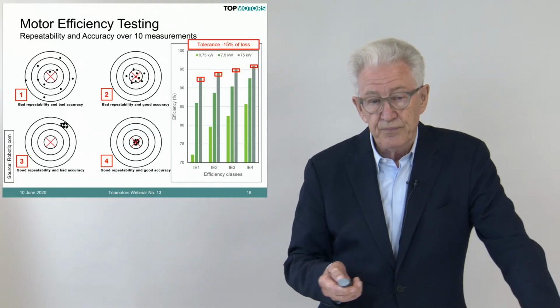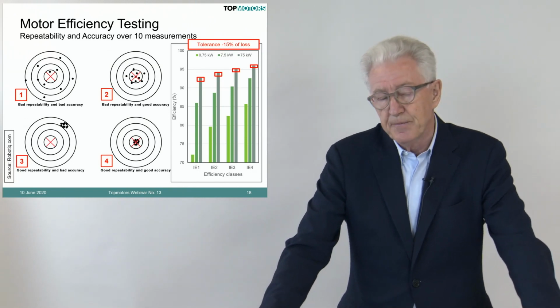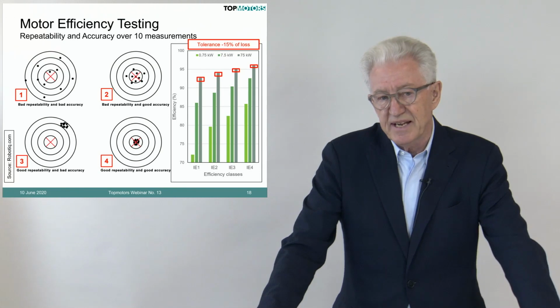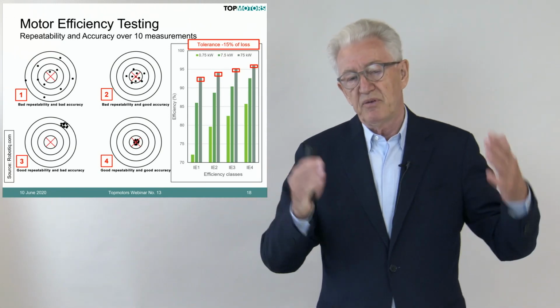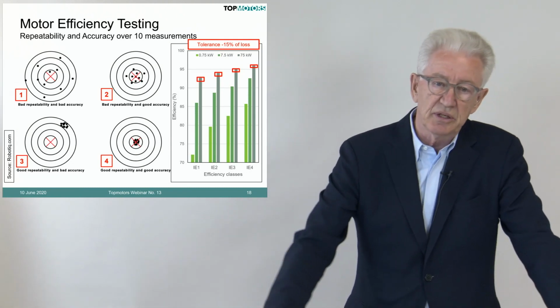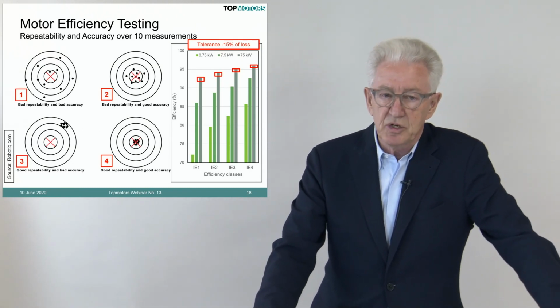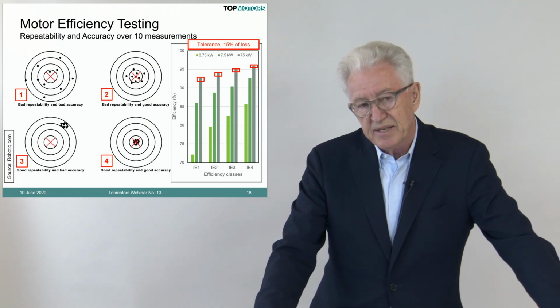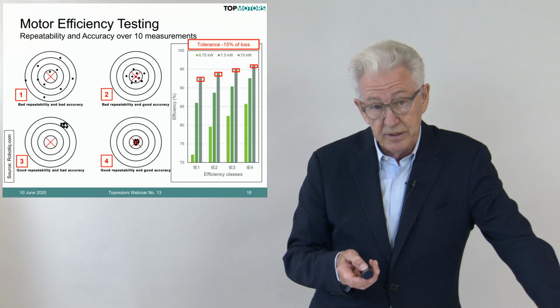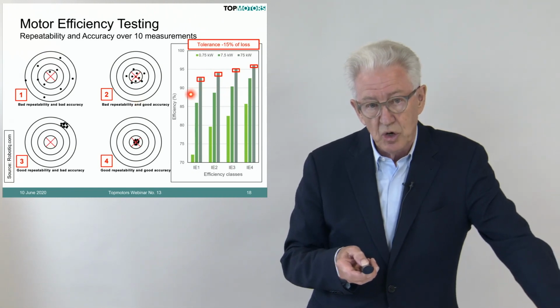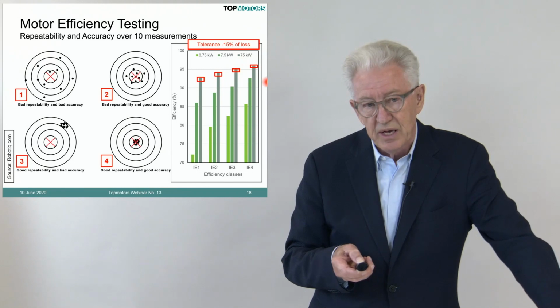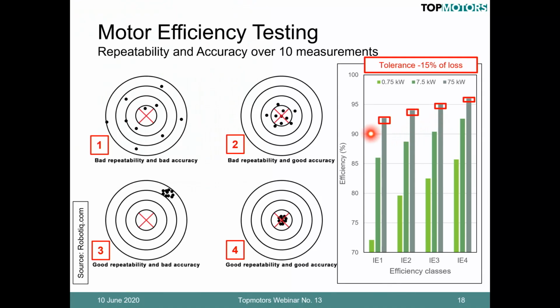Now, when I show you this, the tolerances. When you look at the tolerance, every motor test has a tolerance. And basically, between the very small ones and 100 kilowatt, 150 kilowatt, we talk about 15% tolerance of the losses. The red little squares I show on the top of, in this case, the 75 kilowatt motor, show what is the deviation that is allowed. And now when you look at it very closely, when you make the picture big again, you see that the tolerance of this one, IE2, the bottom line, is very close to the upper line of the IE1. That means the tolerances are relatively sensitive.